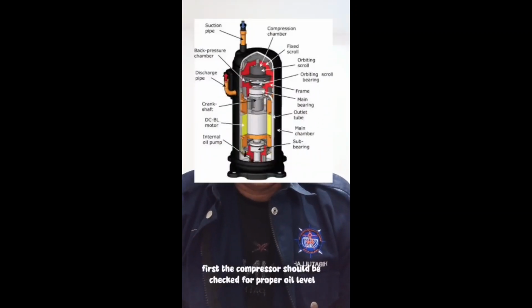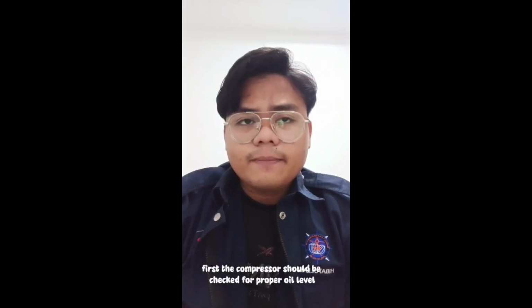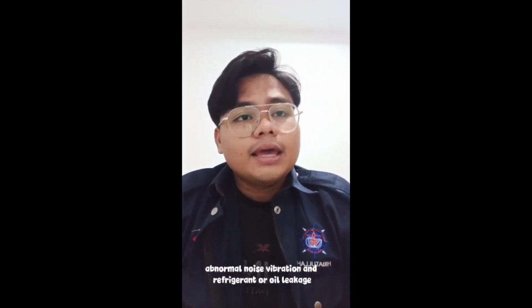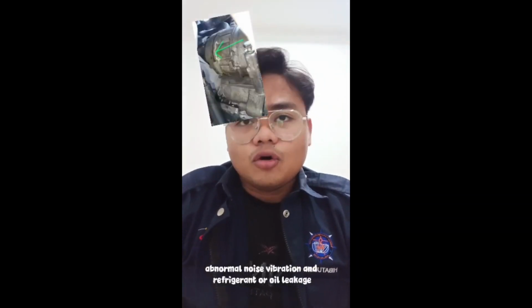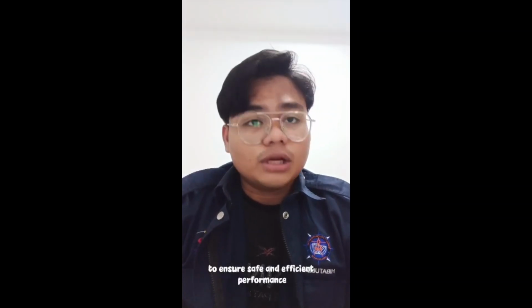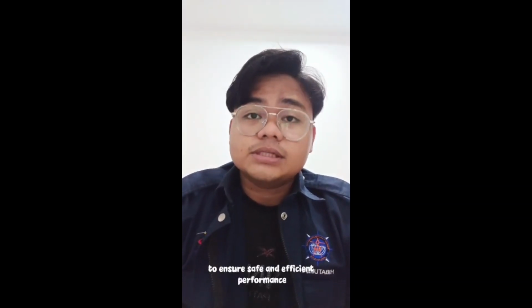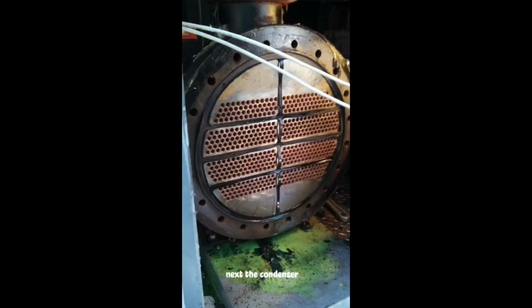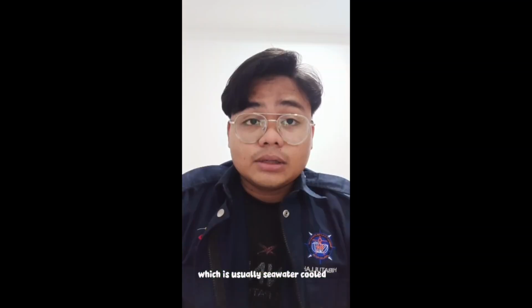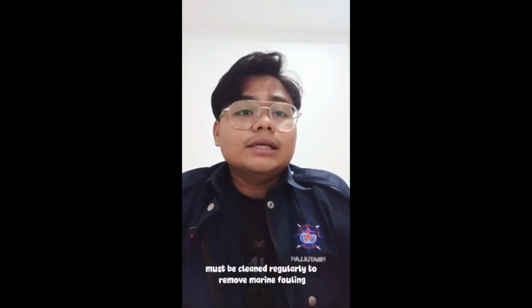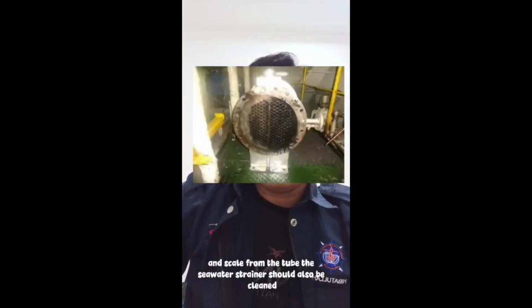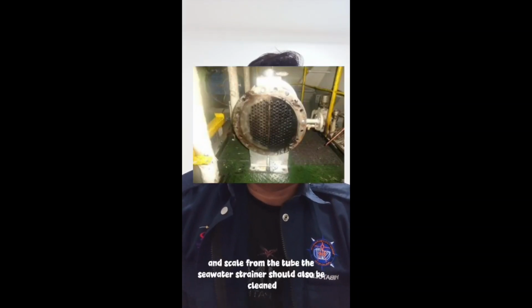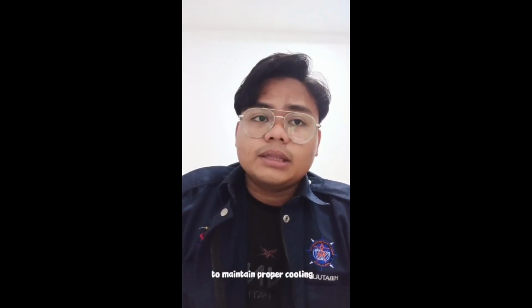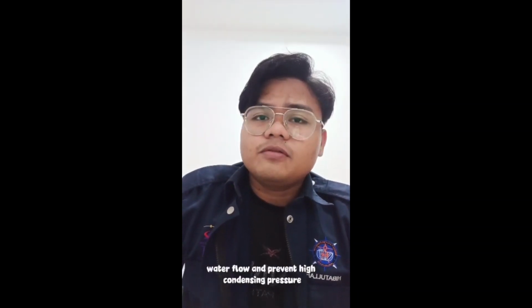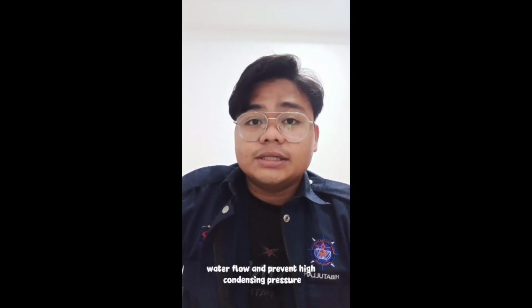First, the compressor should be checked for proper oil level, abnormal noise, vibration and refrigerant or oil leakage. Operating pressure must be monitored to ensure safe and efficient performance. Next, the condenser, which is usually seawater cooled, must be cleaned regularly to remove marine fouling and scale from the tube. The seawater strainer should also be cleaned to maintain proper cooling water flow and prevent high condensing pressure.